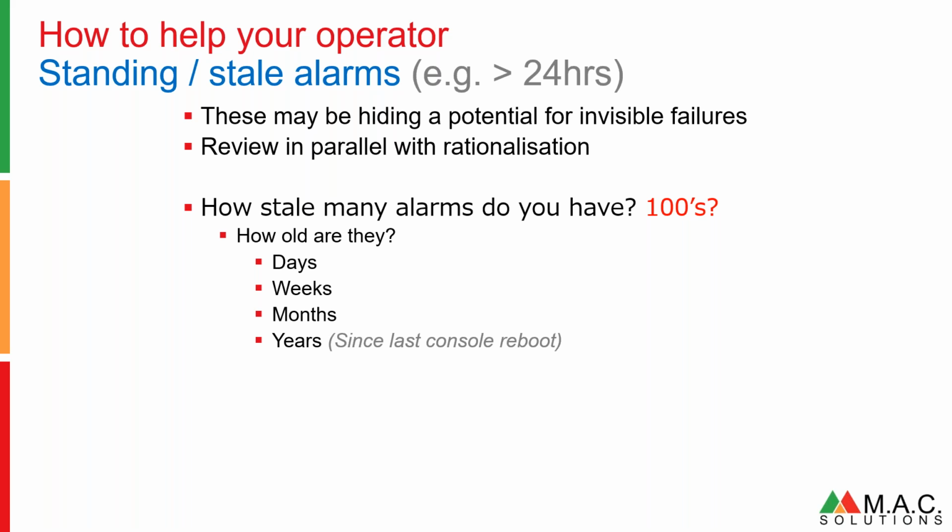Seriously, genuinely, honestly, I was asked, "Where did you park your car this morning?" I said, "In the little car park." "In the tiny little car park, you turned left off the roundabout and you came through the security lodge?" I said, "Yeah." "That's where those alarms are from. That was where the flash gas compressor used to live. We got rid of the flash gas compressor about 15 years ago. So those 4 pages of standing alarms that you see on the console are actually from about 15 years ago." "Oh, yeah, we've told them. Nobody ever does anything. They just sit there."